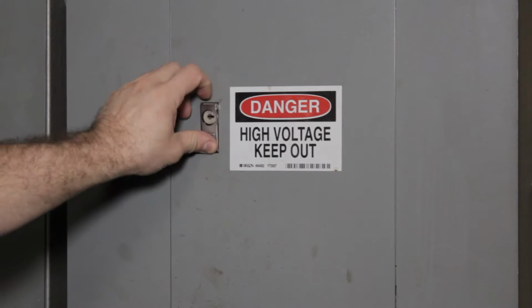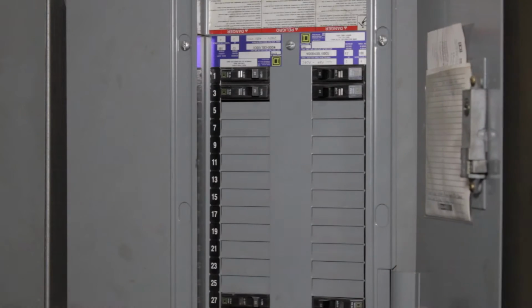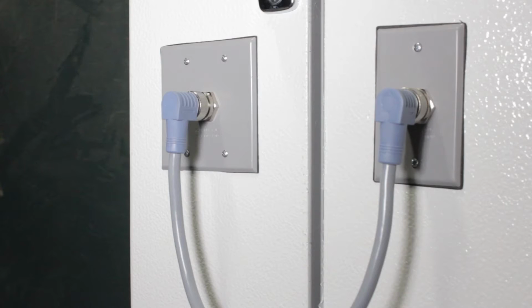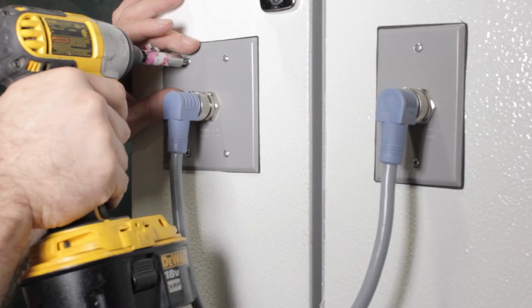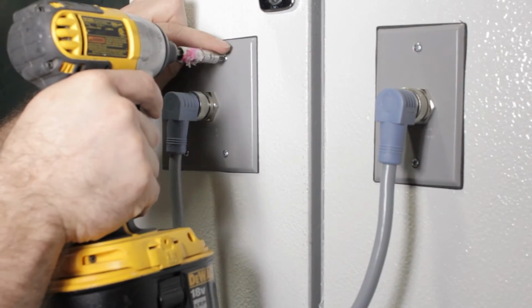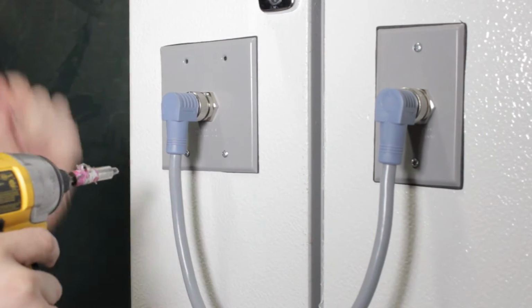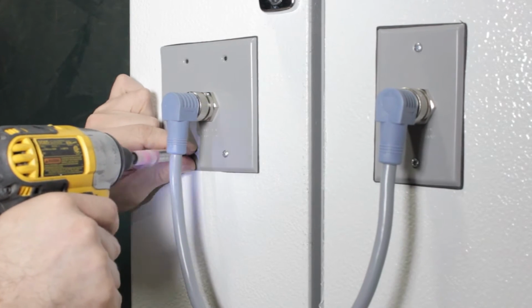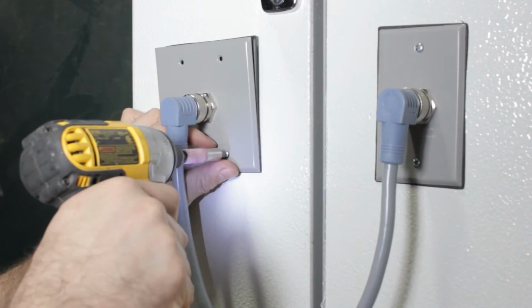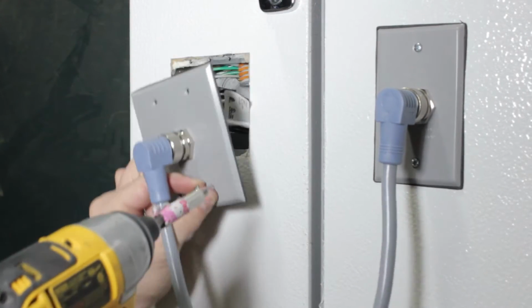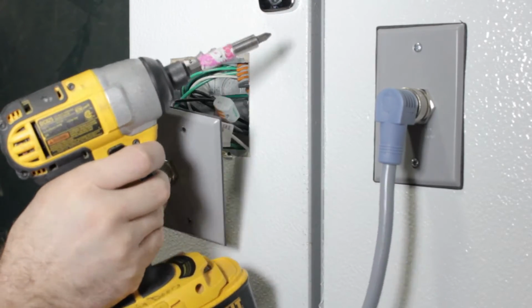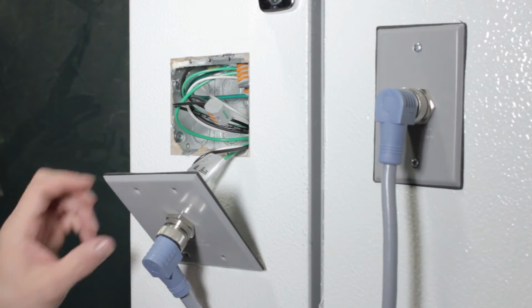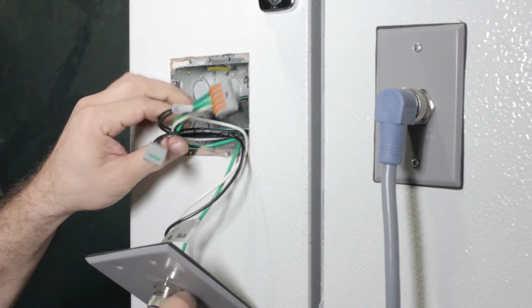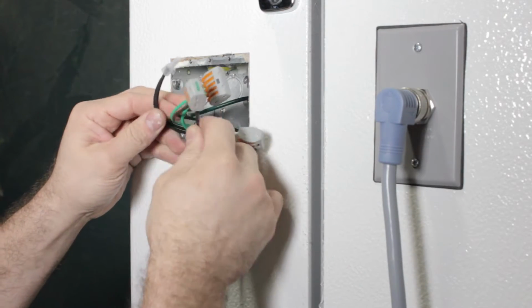First, remember to turn off the power to the swing door heater cable at the main circuit breaker. Then use your drill to remove the 4 screws holding the cover plate on the junction box. Store the 4 screws in a safe place for replacement at the end of the job. Reach into the junction box and pull the electrical wires out.